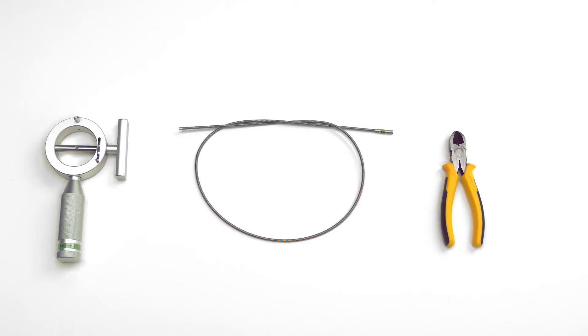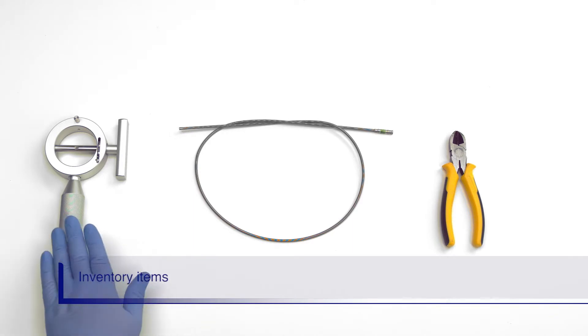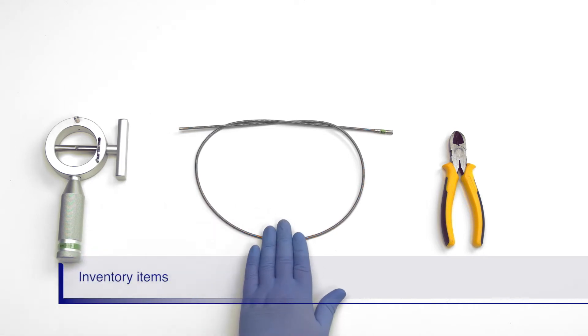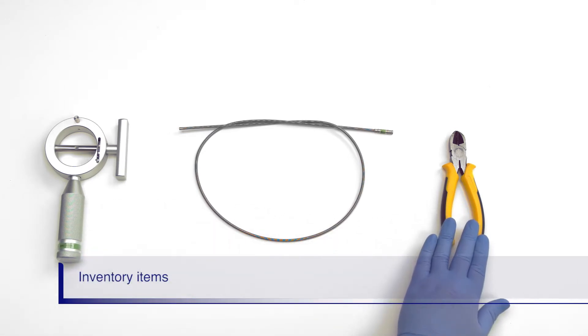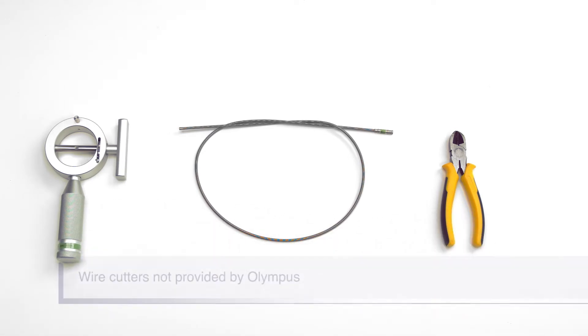Before we review the procedure for the emergency lithotriptor handle, we will need to inventory our supplies. You will need the emergency lithotriptor handle, coil sheath, and wire cutters. The wire cutters need to be of good quality. Bandage scissors will not work.